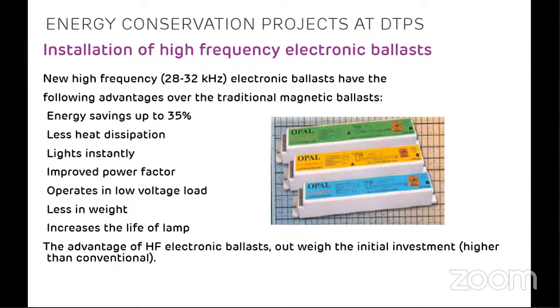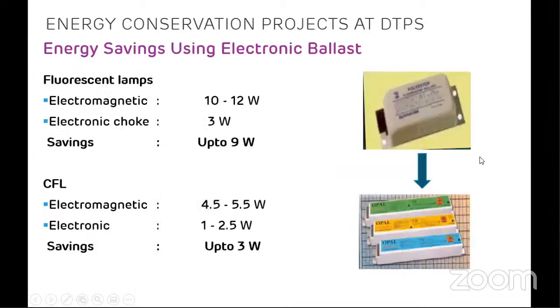Therefore, all of the benefits far outweigh the initial cost. The initial cost of electronic ballast is comparably higher than the copper ballast, but their benefits are much more. So see, if you install a 10 to 12 watt electromagnetic ballast, and instead replace it with an electronic ballast of 3 watt, there is a 9 watt saving. And in case of CFLs, if a 5.5 watt electromagnetic ballast is replaced by a 2.5 watt electronic ballast, that is 3 watts of energy saving. Compared to all other earlier projects, this saving is very small. But like I said, every watt of energy saved is important to us.